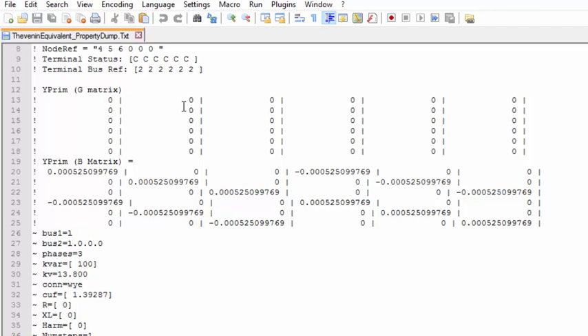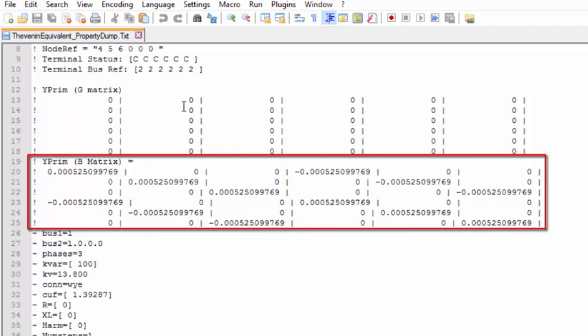Now, you might be asking yourself, why are there six nodes in this matrix? As explained in the Y-matrix tutorial video, the answer is because the Y-primitive matrix relates the injected currents and the nodal voltages of the element, regardless of any possible connection to ground. Besides that, differently from the load element, that is a power conversion element, the capacitor element in OpenDSS is a power delivery element, which means that it can be connected between two buses in a series connection, like a line, for example.